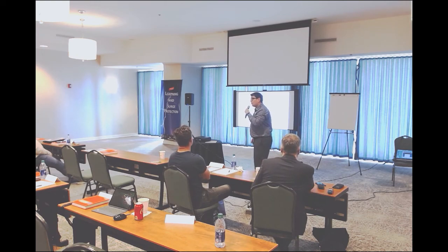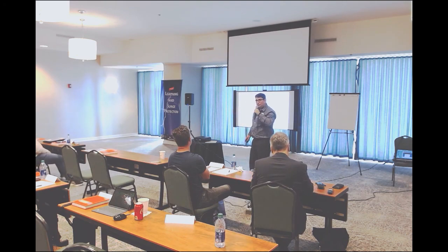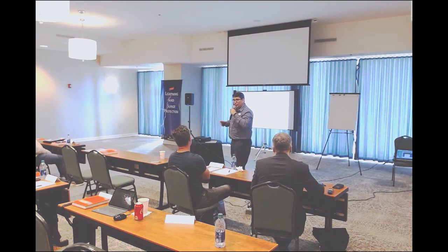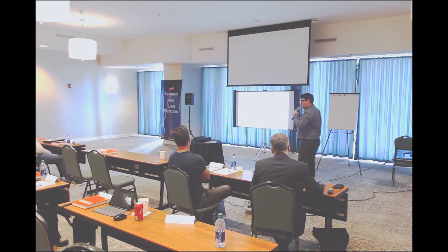It's really nice to quickly be on top of a building, see what the relevant components on the building are and what you want to protect, and then measure those distances, and it'll be easy to tell a client while you're on the roof that it looks like you're looking at about 6 rods spaced equivalently, these X amount of distances, and that way you can make sure that the rolling sphere does not touch the roof of the structure. And the same for the protective angle method. There you can give the client an idea what the height of the air termination rod is relevant to whatever protection method he needs.